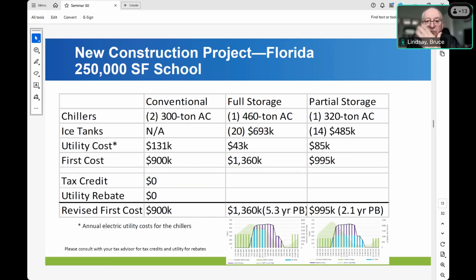A conventional system for a 600-ton load would be 2 300-ton air-cooled chillers. That's going to cost roughly $900,000, and the utility cost will be about $130,000 per year. If they go over to partial storage, that's my cheapest option using storage. I downsize my chiller, but I add a bunch of tanks. I have a premium of $95,000, but I'm saving roughly $46,000 a year. That's a 2-year payback. That's not bad.